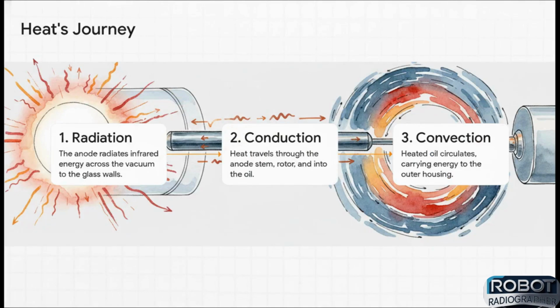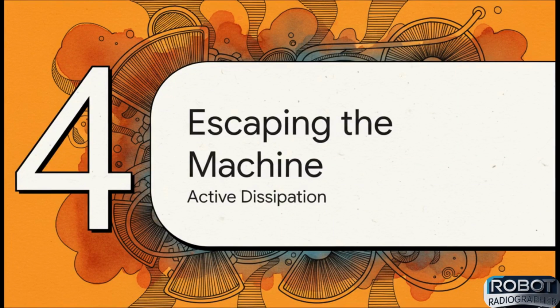So if we recap the heat's journey so far, it's really a three-step dance. First, the superhot anode radiates that energy out as infrared waves. Second, heat conducts right through the metal stem of the anode itself. And third, the oil circulates through convection, carrying the heat away from the tube and toward the outer housing. Okay, so at this point, we've successfully moved the heat from a microscopic point on the anode to the entire outer casing of the machine. But here's the thing: containing it is only half the battle. Now we actually have to get rid of it completely.